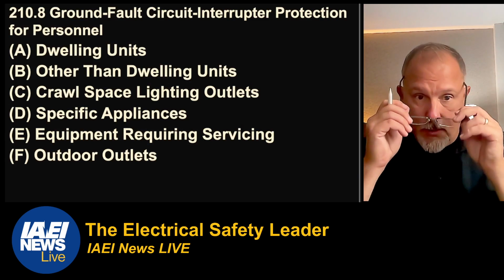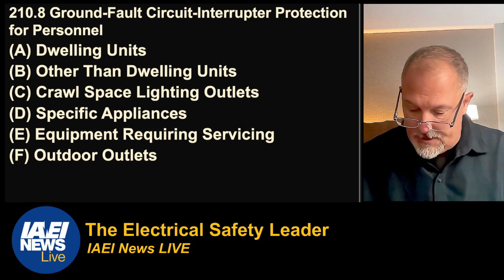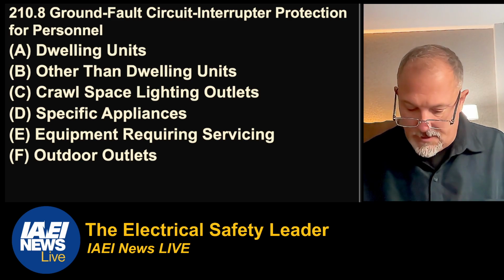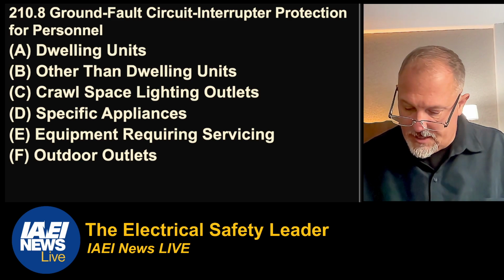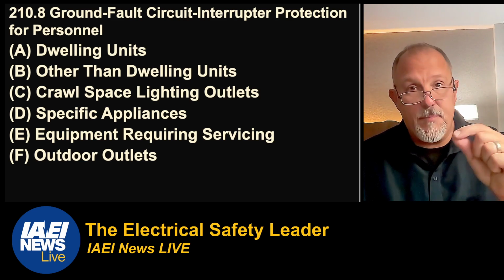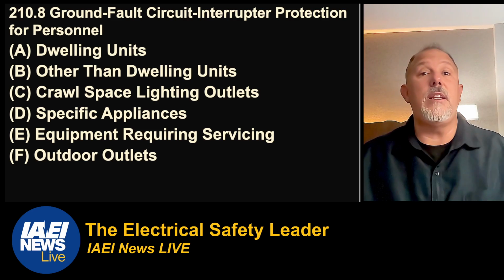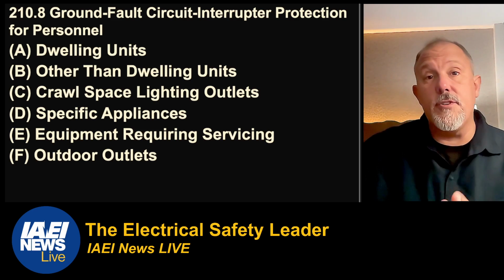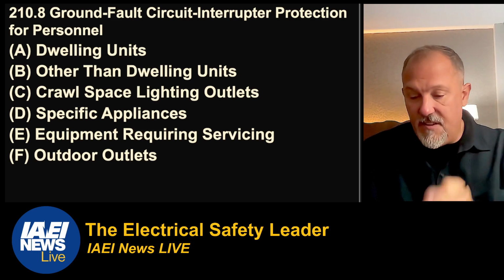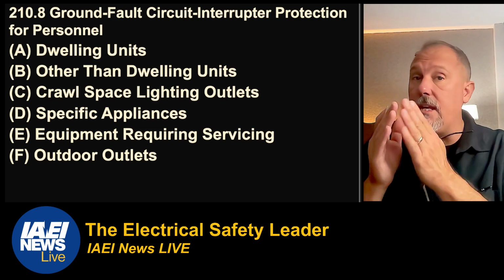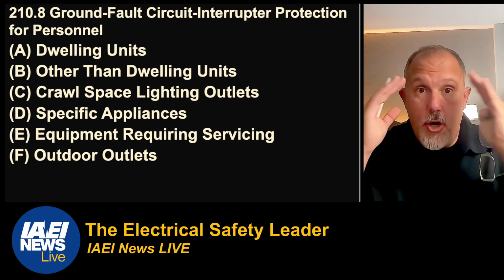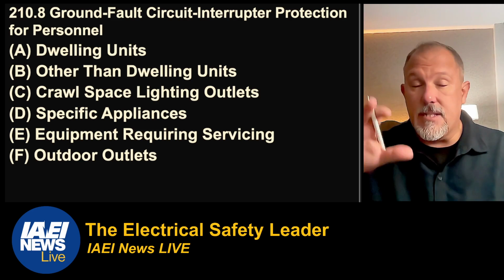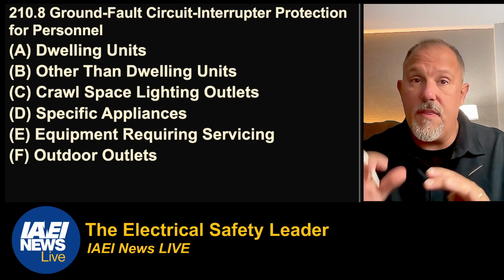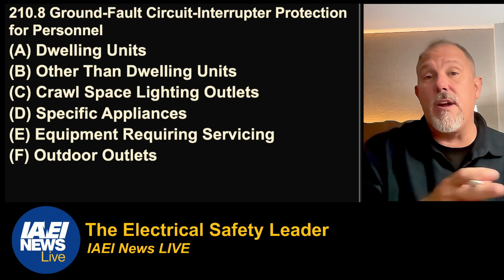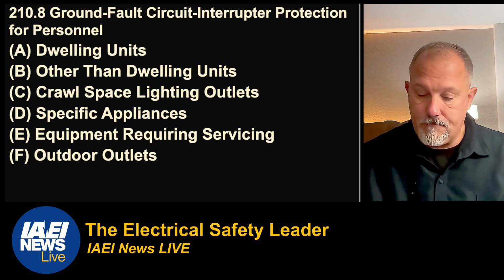So you'll see 210.8. I just have to get to the right location here. /70 next. If you want to follow along, remember you can go to www.nfpa.org/70 next, and you can see the first and second draft. If you really want to understand the code changes and you're looking at NFPA's website, you've got to look at the first draft and the second draft. You can't just go to the second draft unless you know exactly all the words for each of these sections. The second draft may not provide you with the underline and strikeout for the changes that occurred in the first draft that didn't change in the second draft. So keep that in mind.